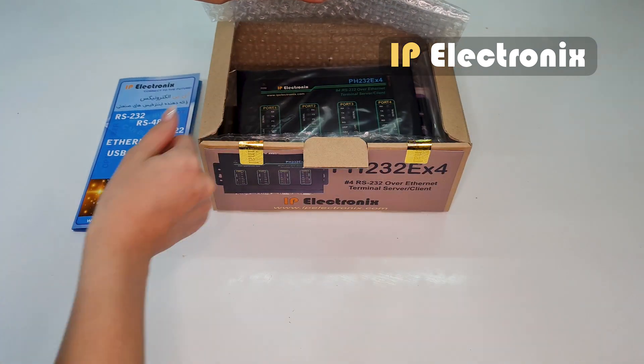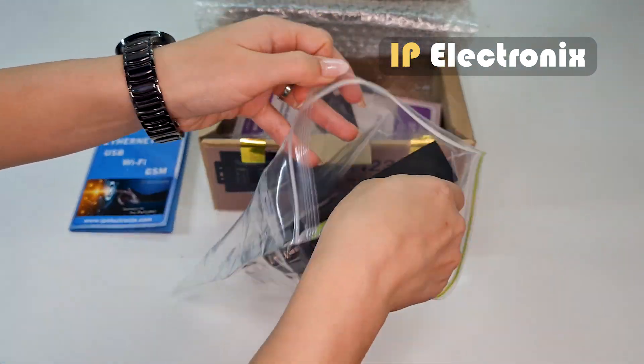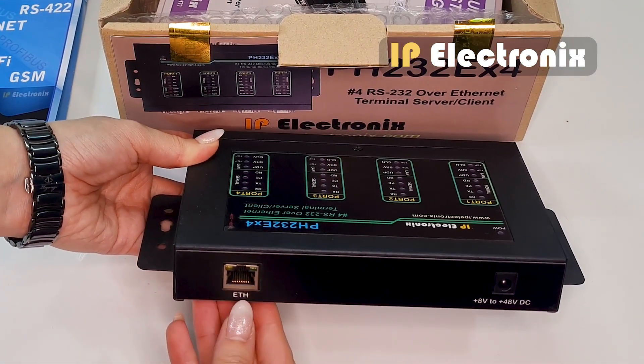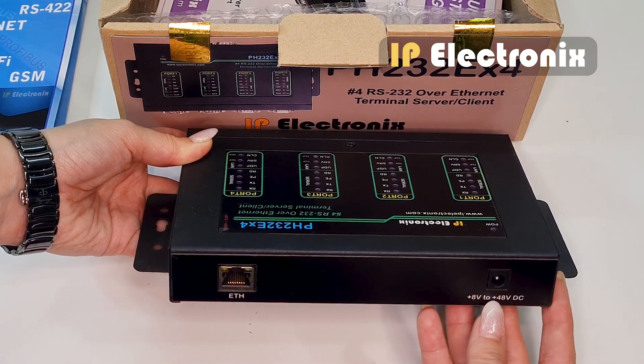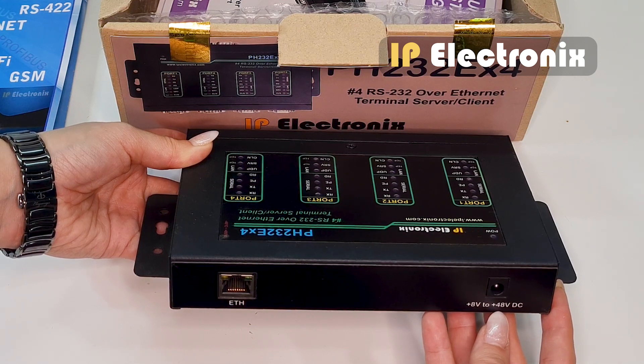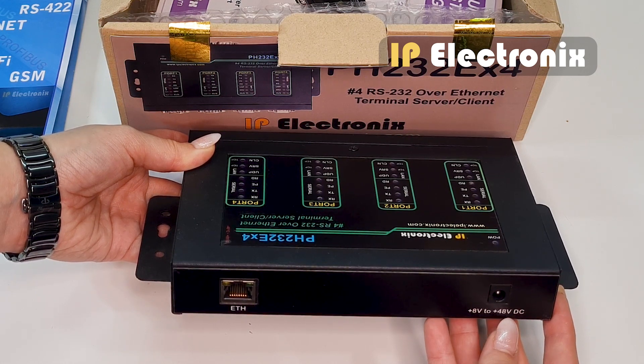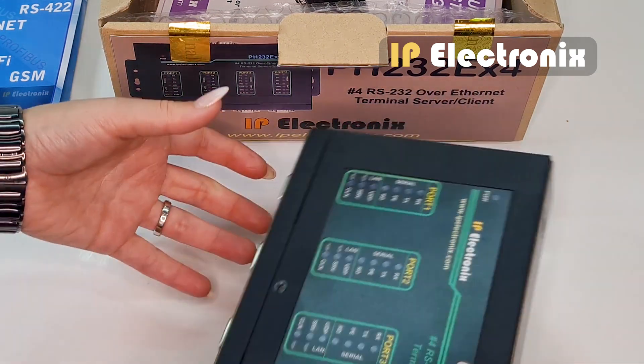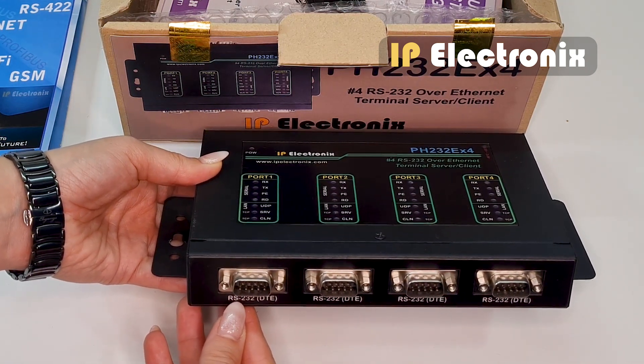This is the product packaging. The contents include a PH232EX4 — I take it out of the plastic cover. On one side it has an Ethernet port with an RJ45 connector and an adapter jack for the power input. Note that this device can work with any DC voltage from 8 to 48 volts, so you can use any available DC industrial power supply, for example 24 volts DC. On the other side it has 4 RS232 DTE ports with 9-pin DB9 male connectors.